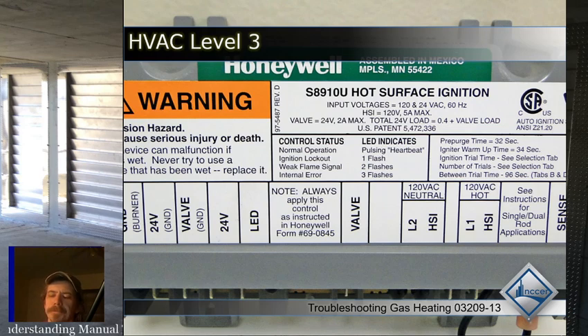So the furnace only operates when it needs to. You have to set some kind of point where the heat pump goes off and the furnace comes on. And the thing is that's going to be different for every house. Okay, every single house or building for that matter is going to be different where you need to cut off the heat pump and turn on the furnace. That is because a heat pump puts out different amounts of heat based on outdoor temperature. So if it is 70 degrees outside, we can pick up a ton of heat from the outdoor air, right? Because it's 70 degrees outside, so there's plenty of heat for that outdoor unit to pick up and take inside. Remember, a heat pump picks up heat from the outside and takes it inside. Okay, so we're picking up heat from the outside air and we're giving off heat to the inside air.